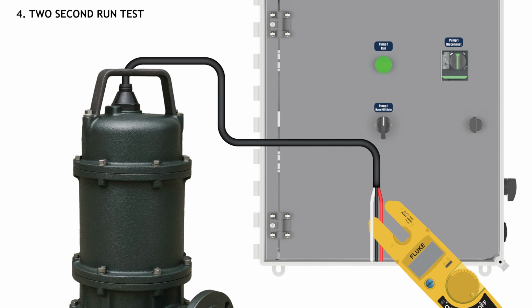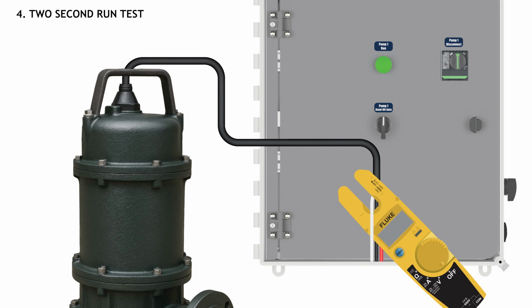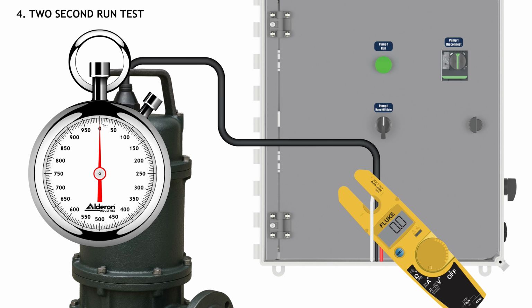Place the amp meter on the main winding of the pump that is connected to the terminal block that is marked main, which is inside the control panel. In this hypothetical example, let's say we have a 2-horsepower pump with 15 full load amps, as shown on the pump's nameplate or in the pump's owner's manual. Note, full load amps will be higher for high horsepower pumps. The main point is that the amp reading from the 2-second test should not exceed the full load amps of the pump being tested. Second, place the HOA switch to hand for 2 seconds and note the amp reading.